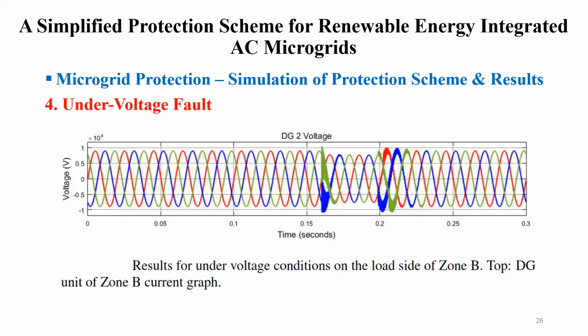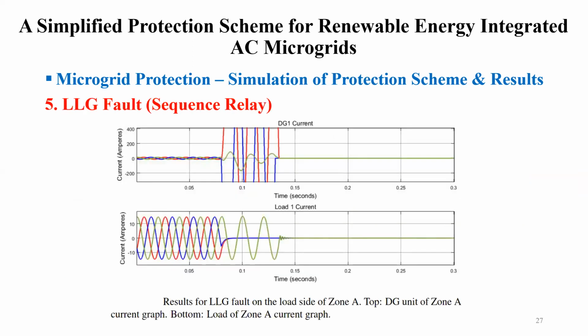Then here we see the under and over voltage faults. In this case, again, we see a fault coming at 0.16 seconds. Once the fault is removed, the voltage levels come back to normal, and that is again achieved within 0.1 seconds. That is within the prescribed standard limits for fault correction.